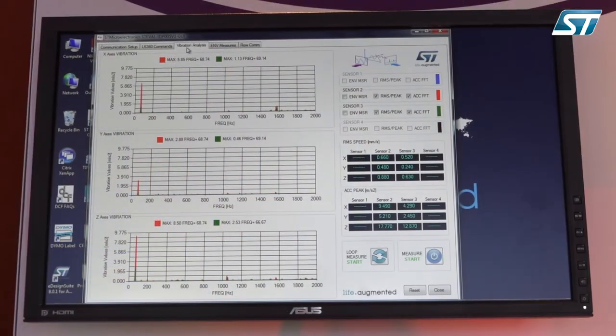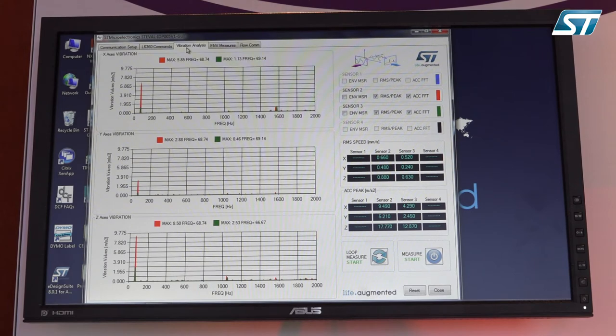These two boards are mechanically connected to each of the motors but not electrically. So they can perform an analysis of the vibrations ongoing in the motor and also of the environmental parameters. Once the analysis is performed, we can see frequency by frequency — up to 2 kHz in this case — the behavior of each of the two motors presented with a different color.